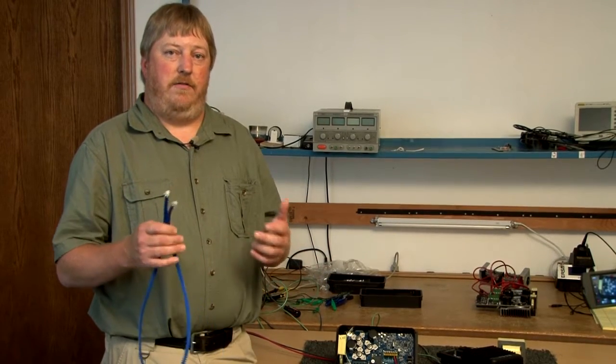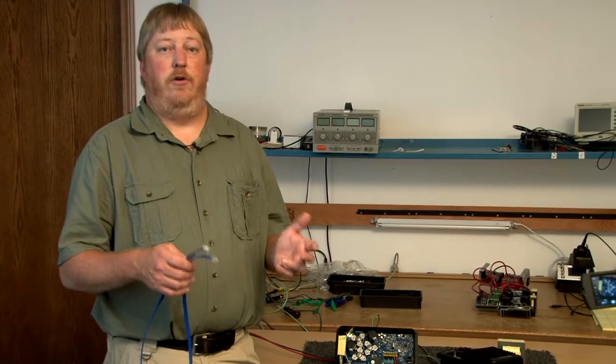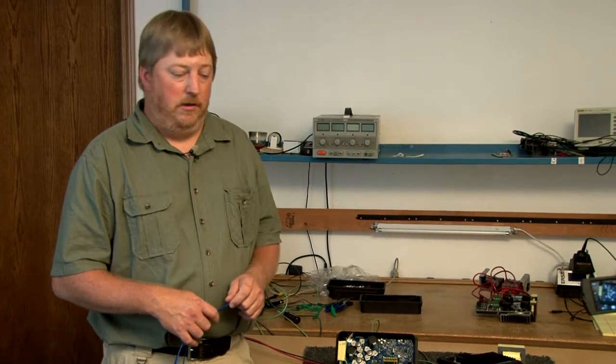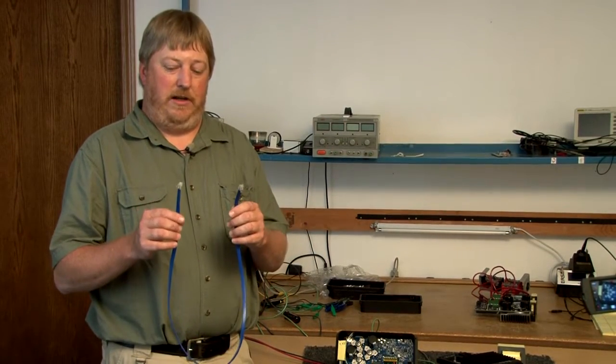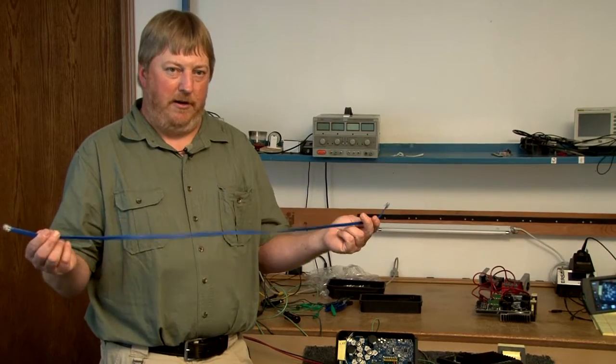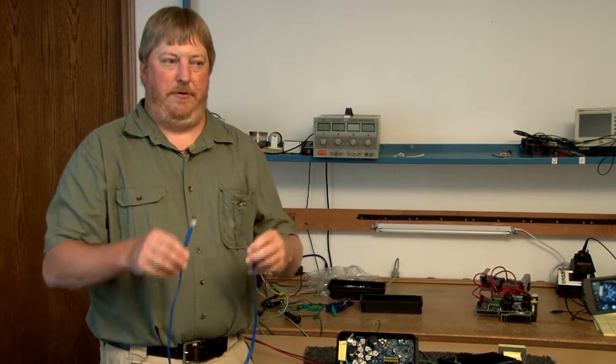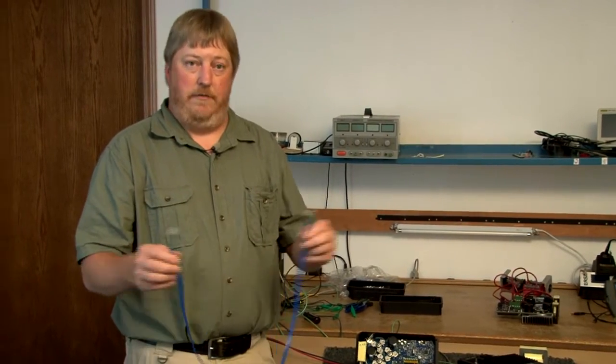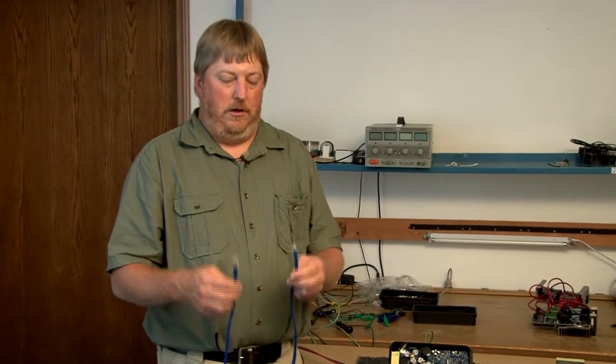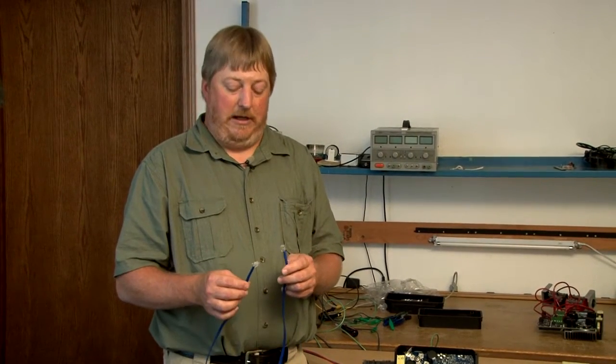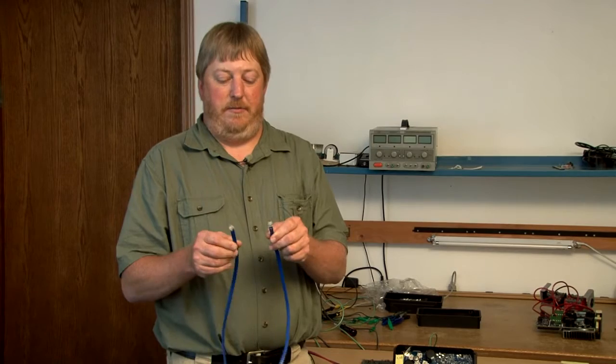I do want to point out that you're going to need firmware version 1811 or newer for both of these modes. You will need a six conductor phone cable. Something I want to point out about this cable, this particular cable can be purchased from our website if you're in a bind and need to make your own. A phone cable, when they call it a straight through cable, becomes a mirror image from one end to the other.